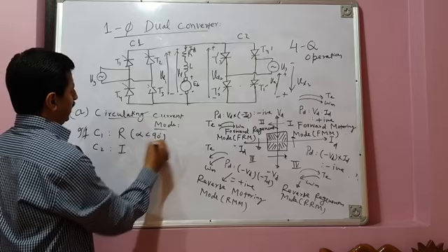Similarly, if you want to take your machine from reverse motoring mode to forward motoring mode, you have to brake it first. So to go from quadrant 3 to quadrant 1, you have to go through quadrant 4. In quadrant 3, your machine is running in reverse motoring mode. Then you go from quadrant 3 to quadrant 4, where your machine operates as a generator, in regenerative braking. Of course, reverse regenerative mode will take place. The machine slows down and comes to a stop. Once it comes to a stop, you move to quadrant 1, where it again runs in the forward motoring mode.